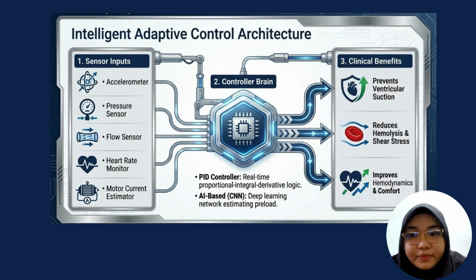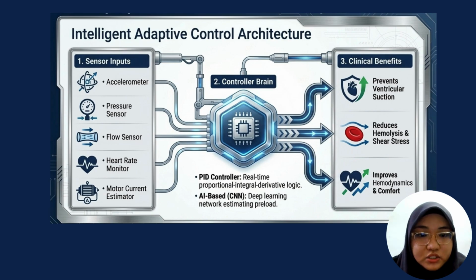So, when the patient transitions from resting to exercising, body movement, venous return, and heart rate increase. These physiological changes are detected by the sensors and sent to the controller. The controller then processes the incoming data using either a PID controller or an AI-based adaptive algorithm. Based on the physiological demand, the controller gradually increases the pump rotational speed to provide greater blood flow and maintain adequate systemic circulation. During resting condition, the controller reduces pump speed to prevent excessive ventricular unloading and minimize power consumption.